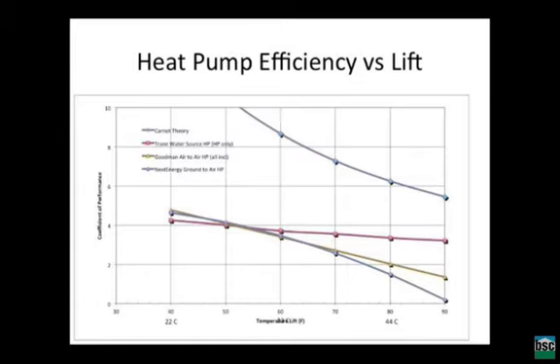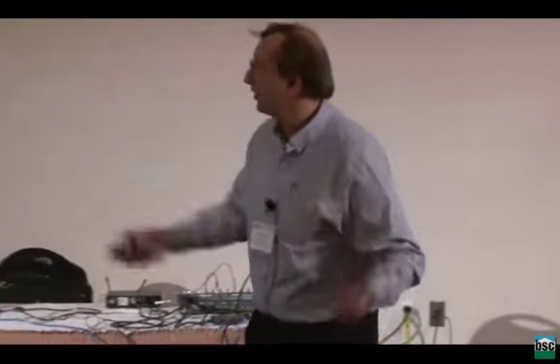So if you're trying to heat the building and the compressor is outdoors, you lose the heat that you put into the compressor motor. And in fact, that's often how they fail. If you ask them to lift too much and run them all the time, they will trip out at high temperature. Because they'll get to 160 degrees, 180 degrees, you'll actually melt the windings, the insulation of the windings, and that's how they die. Otherwise, they'll just keep running, right? No matter if you put them in Antarctica, they'll keep running. So they have to be protected from trying too hard, because they'll heat up, but their efficiency can be less than 1.